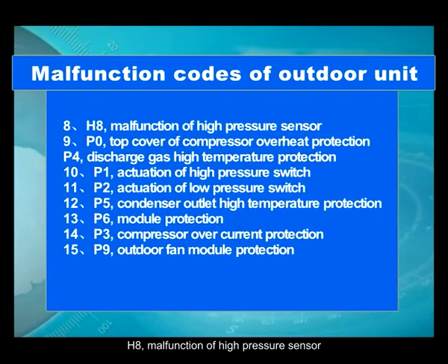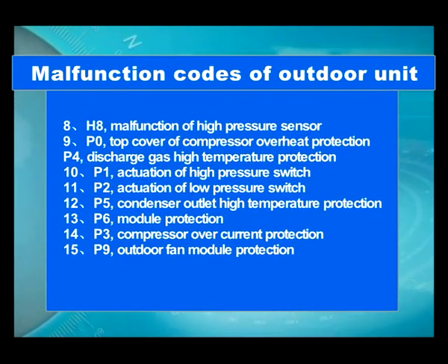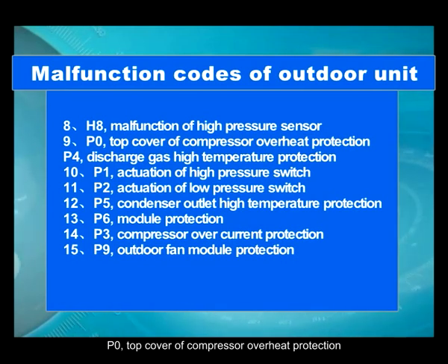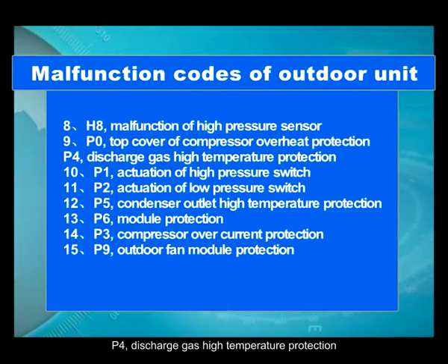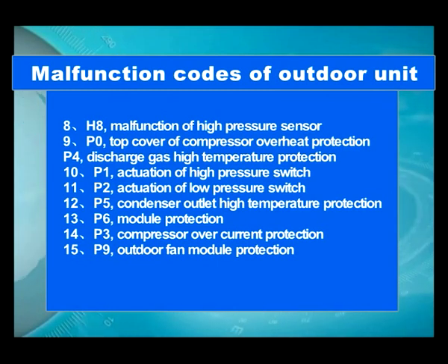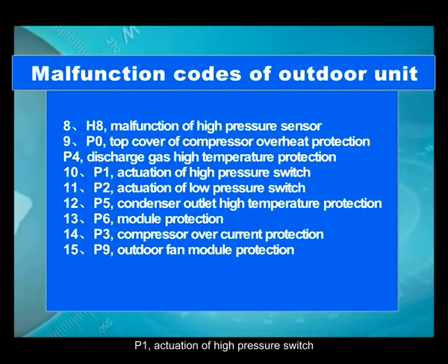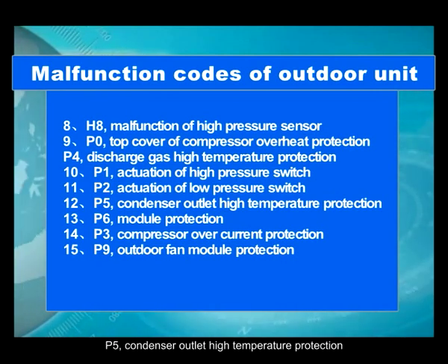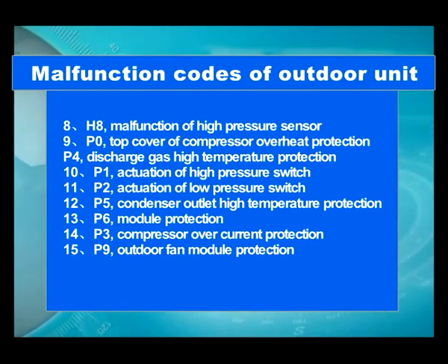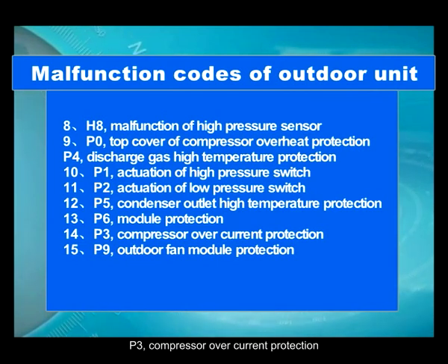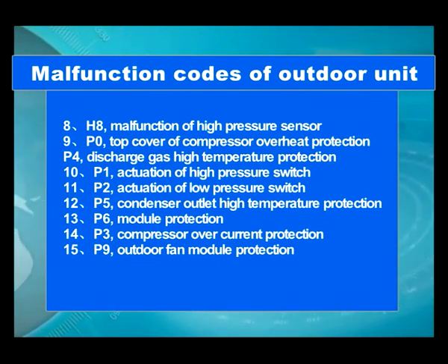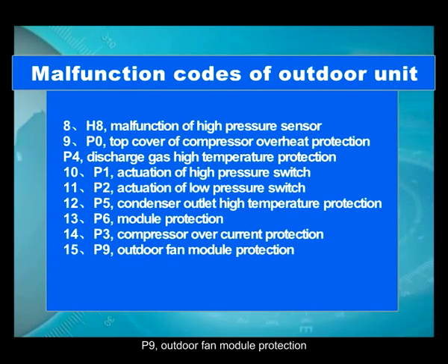H8. Malfunction of high pressure sensor. P0. Top cover of compressor overheat protection. P4. Discharge gas high temperature protection. P1. Actuation of high pressure switch. P2. Actuation of low pressure switch. P5. Condenser outlet high temperature protection. P6. Module protection. P3. Compressor over current protection. P9. Outdoor fan module protection.